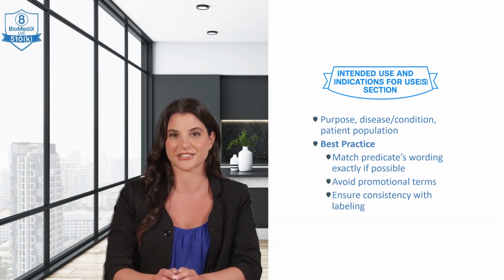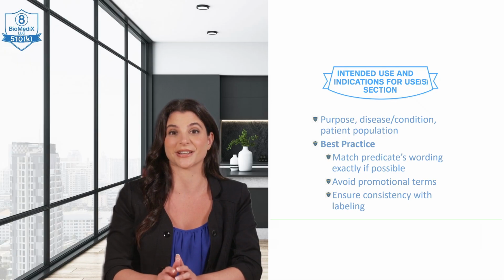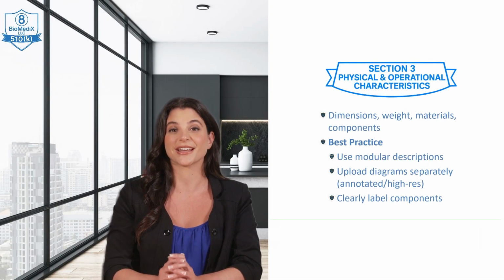The best practice is to be precise and concise. Avoid promotional language. Ensure your indications for use are identical to your chosen predicates, or that any differences are thoroughly justified in the substantial equivalence section.